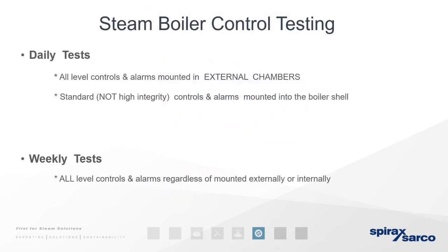So daily tests, the tests you should be doing on your boiler, is minimum. All level controls and alarms, mounted external chambers, should be checked. Standard, not high integrity. High integrity would be something else in controls. They should be checked on a regular basis to make sure they're working correctly. And it really comes down to two things: how you are mounting the controls and the operating principles. Weekly tests cover all level controls and alarms, regardless of how they're mounted, internally or externally.